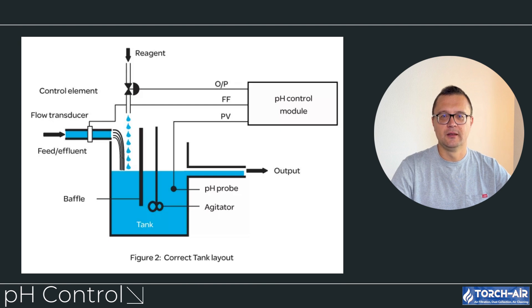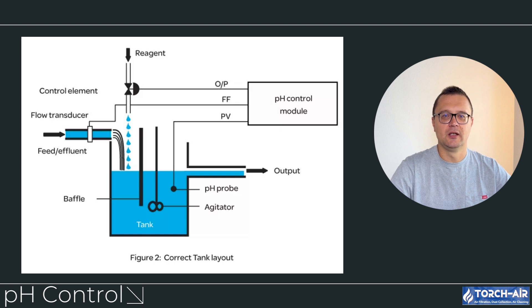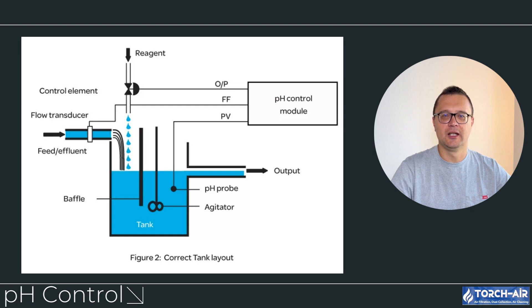pH control. In many scrubbers, especially those used to remove acidic or alkaline gases, the pH level of the absorption solution is critical. Maintaining the correct pH is necessary for the solution to effectively neutralize harmful gases. Automated pH meters continuously measure the acidity or alkalinity of the solution, and when the pH moves outside the desired range, the system automatically doses the appropriate reagents — acid or alkali — to bring the pH back to the optimal level. When a pH imbalance is detected, the automated dosing pump adds the necessary reagents to restore correct pH for efficient gas scrubbing. In cases of extreme deviations, the system can send alerts to operators if automatic dosing fails to stabilize the pH level.